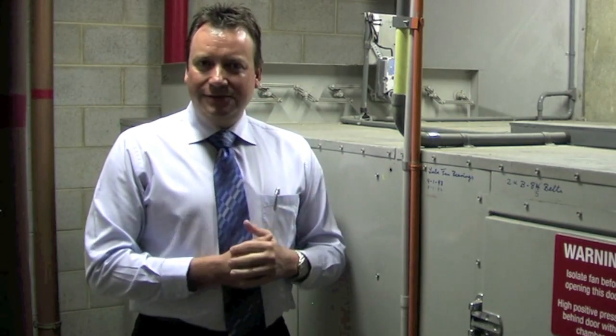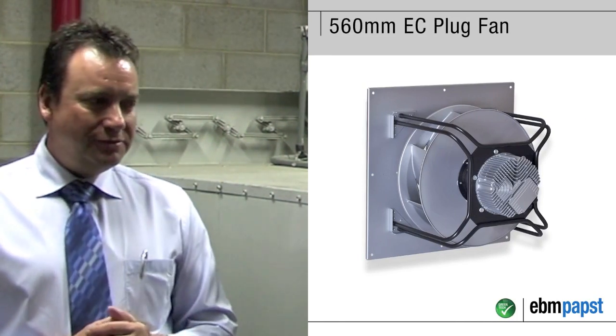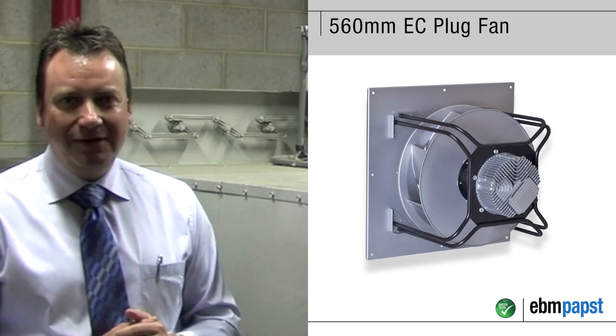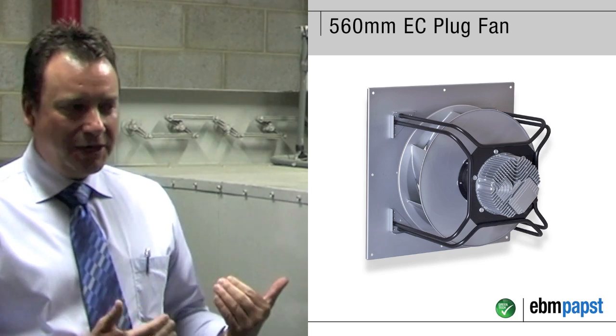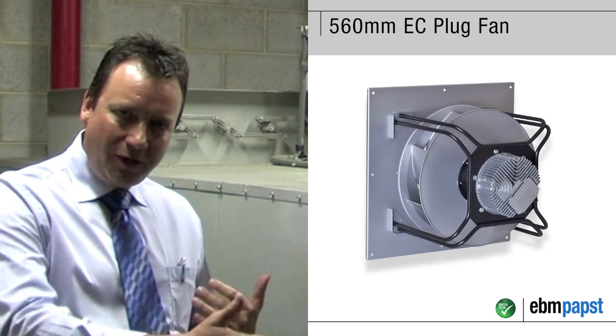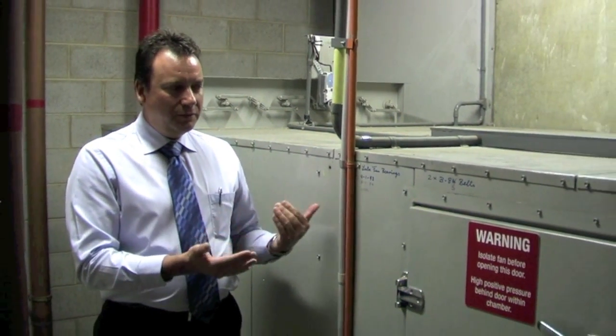We chose level 14 as a sample floor, on which an ebm-papst fan, a 560mm fan, was chosen to deliver 3,800 litres at 800 Pa, in the expectation that we would create a more laminar flow through the coil and that would give us better cooling performance, bringing it back to the more ideal conditions that the coil was originally designed and selected for.